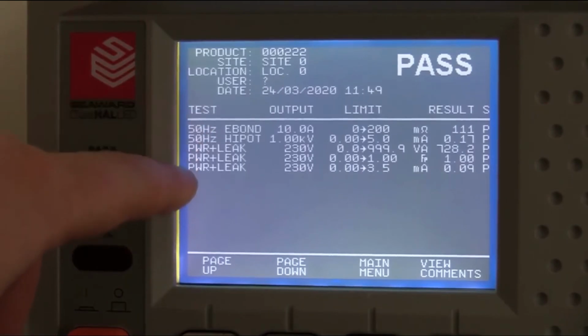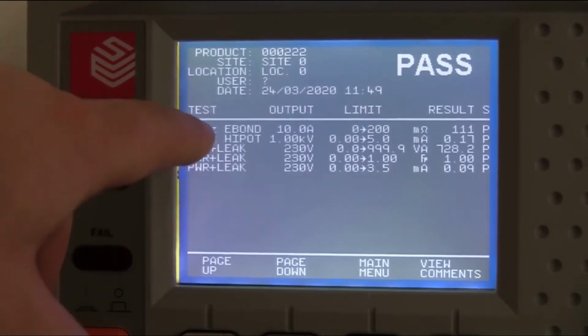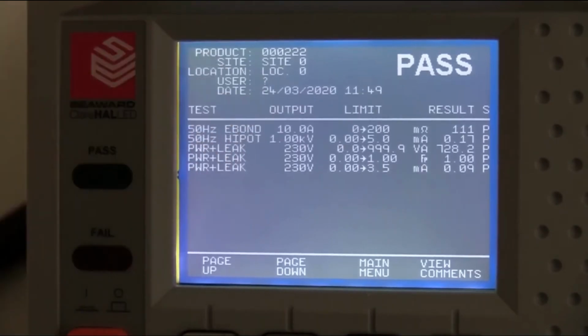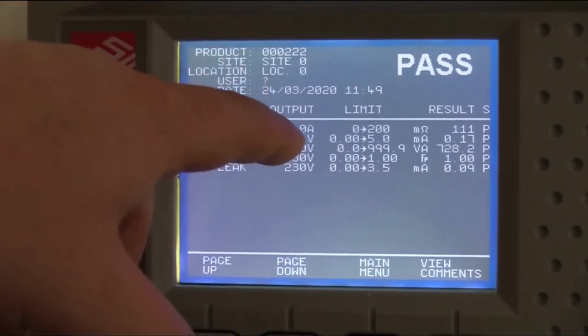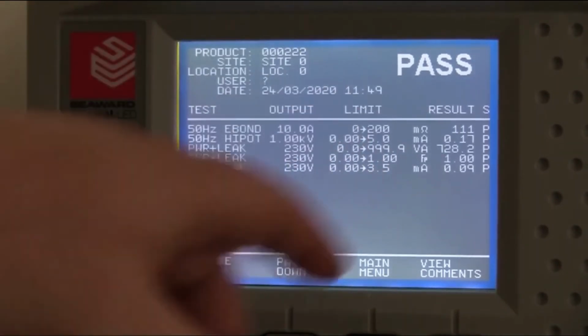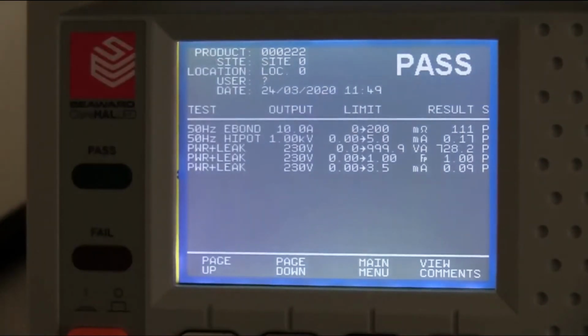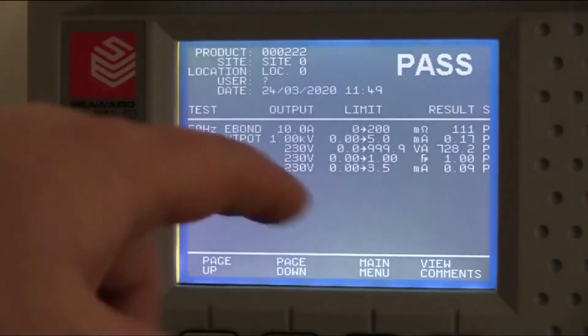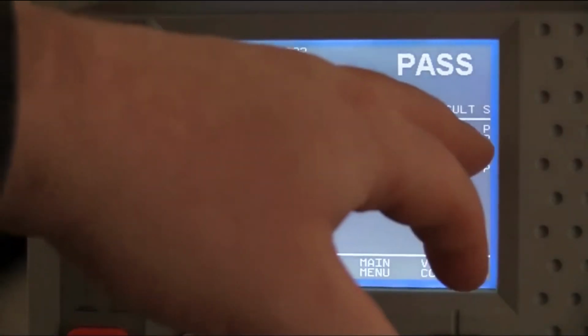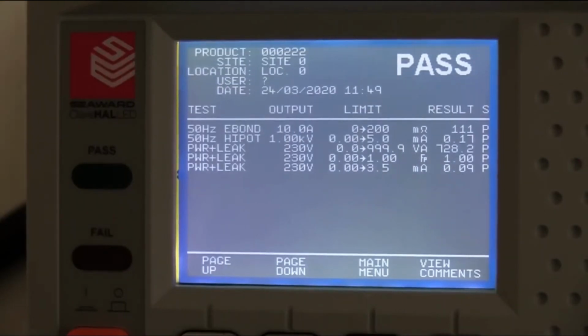So you'll see on the left hand side, these are the tests that were performed. So we have our earth bond, our Hipot, and then 3 measurements for the leakage and power. So we can see we outputted a 10 amp test. The limit was between 0 and 200 milliohms. Our measured value was 111 milliohms, therefore the unit passed. Similarly for the Hipot, our output was 1 kV. Our limit was 5 milliamps. The unit measured 0.17 milliamps, and therefore it passed. So all of this is now stored within the memory of the HAL, and it can be freely downloaded, transported to a PC for digital record keeping.